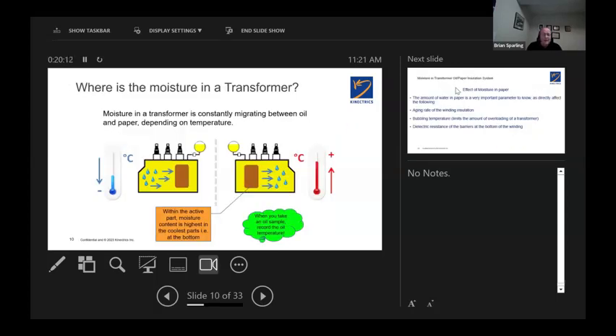Now, in the transformer, the moisture is constantly moving back and forth between the oil and paper, and it's a function of temperature, which is a function of loading and ambient conditions. So if the loading is constant, the temperature is going down, transformer is running cooler, the oil is cooler, it wants to get rid of the moisture, and the paper is there to soak it back up like a big sponge. When it's hot and you're not overloading, but even bringing the transformer up to full load on a hot day, you are pushing now the water from the paper into the oil. And because the oil is hotter, it will hold now more water. So it's this back and forth. So there's a constant movement, and it's slow, constant movement of moisture between the paper and the oil over time, and it's all a function of temperature.